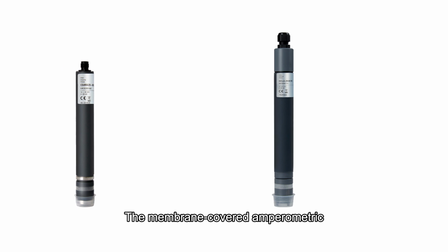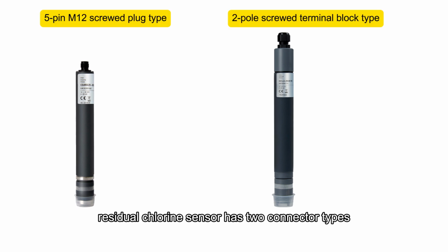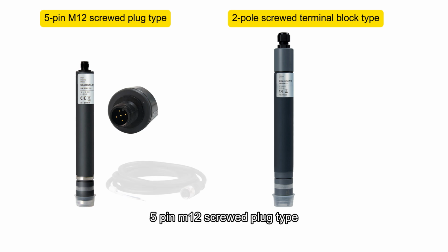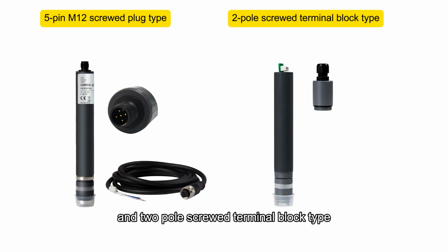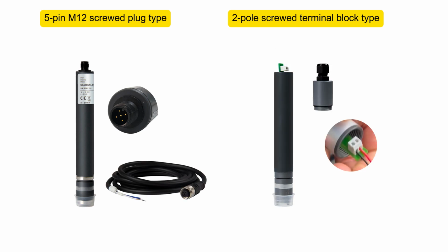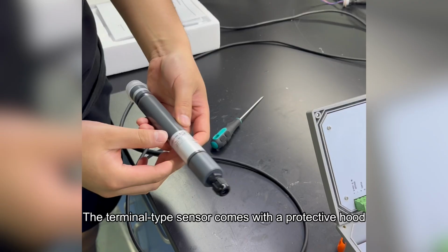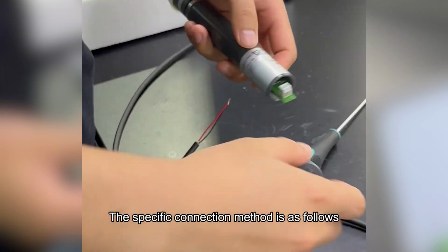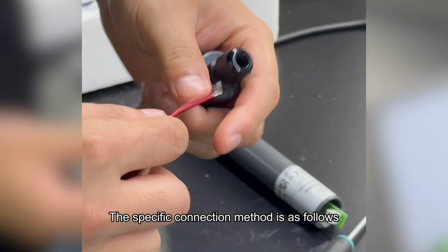The membrane-covered amperometric residual chlorine sensor has two connector types: 5-pin M12 screwed plug type and 2-pole screwed terminal block type. The matching cables are also different. The terminal type sensor comes with a protective hood. The specific connection method is as follows.